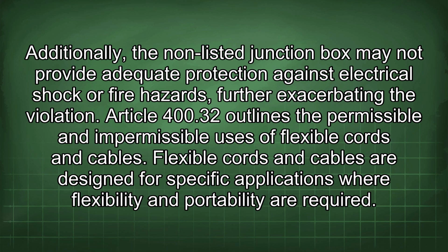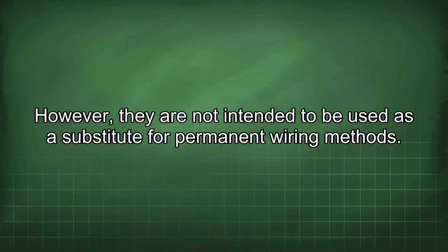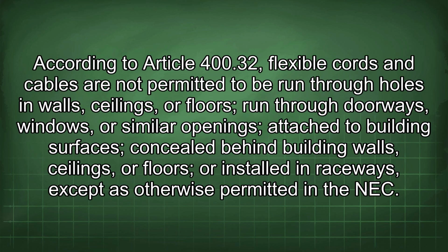Article 400.32 outlines the permissible and impermissible uses of flexible cords and cables. Flexible cords and cables are designed for specific applications where flexibility and portability are required. However, they are not intended to be used as a substitute for permanent wiring methods. According to Article 400.32, flexible cords and cables are not permitted to be run through holes in walls, ceilings, or floors, run through doorways, windows, or similar openings, attached to building surfaces, concealed behind building walls, ceilings, or floors, or installed in raceways, except as otherwise permitted in the NEC.